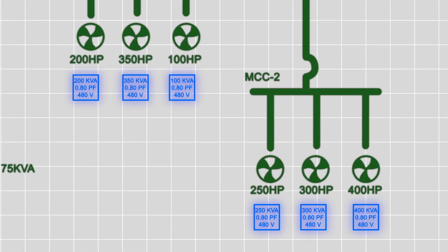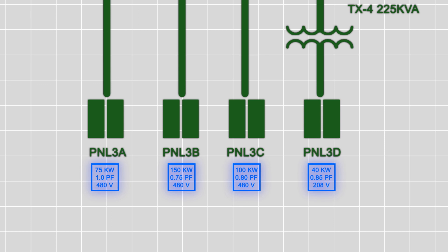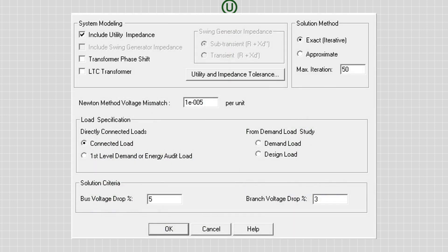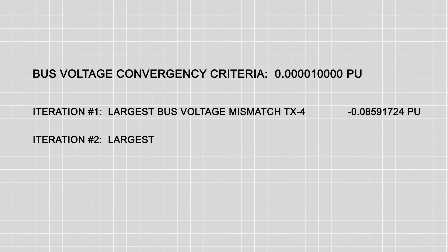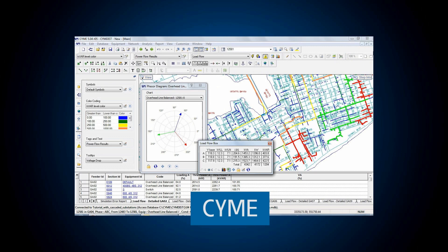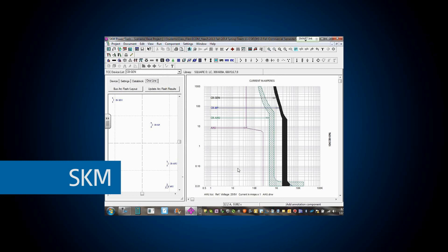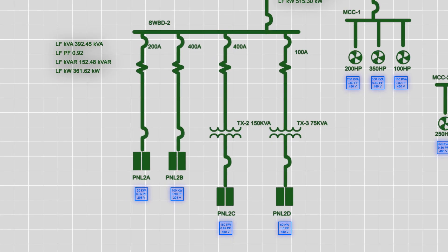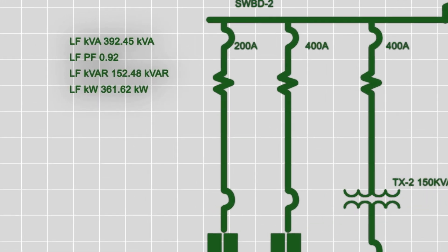The iterative process of a load flow simulation starts by using the load as a known quantity. But since current flow is likely based on voltage, and since the voltage at a particular node varies based on current flow, the program needs to make an educated guess as to the total power flowing from the source. Then calculations are performed until the mismatch of the estimation is very close to the actual load specified. This process used to take many hours for large systems, but with today's computer power, programs like CYME or SKM typically solve the load flow in just a few seconds. Once the load flow simulation is solved, losses and voltage changes along the way are plotted on a single line diagram. This study also reports KW, KVAR, and KVA power flow numbers at each bus so the power factor at various locations throughout the system can be determined and capacitor sizing and placement can be evaluated.